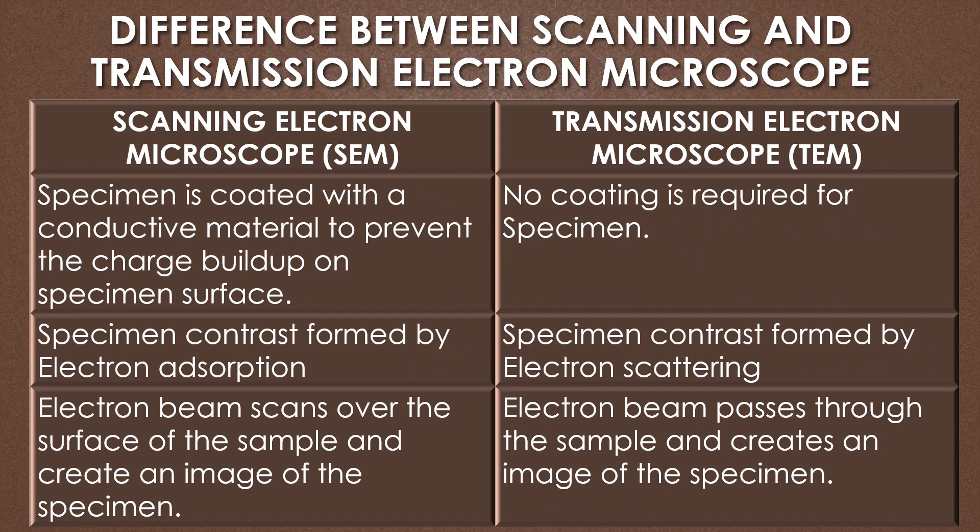In the SEM, the specimen is coated with a conductive material to prevent charge buildup on the specimen surface. In the TEM, no coating is required. Regarding specimen contrast, in the SEM it is formed by electron absorption, but in the TEM the specimen contrast is formed by the scattering of electrons.